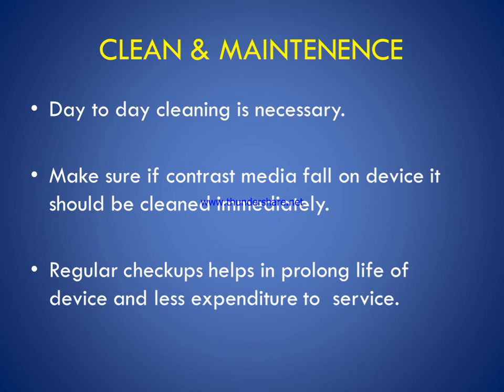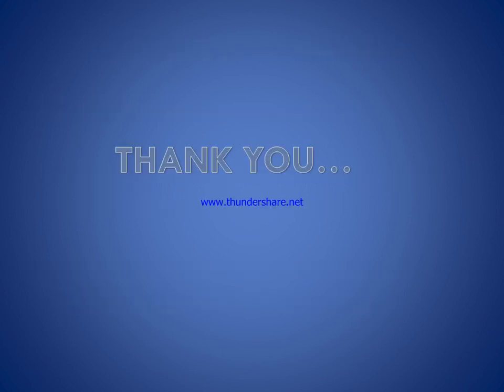Safety features are designed to prevent breaking of the vascular catheter or mechanical malfunction, including pressure limit control, flow rate rise control, mechanical stop, and a high pressure plastic jacket. For cleaning and maintenance of the pressure injector, day-to-day cleaning is necessary. If contrast media falls on the device, it should be cleaned immediately. Regular checkups prolong the life of the device, and less expenditure on servicing.